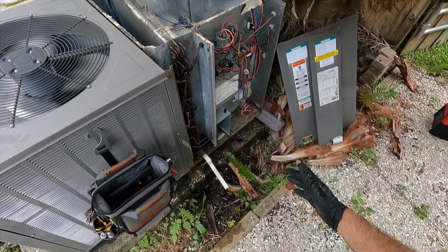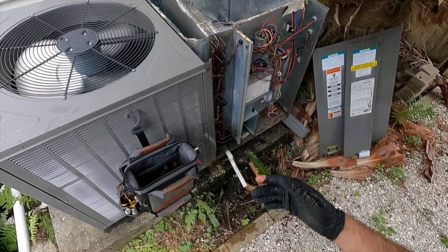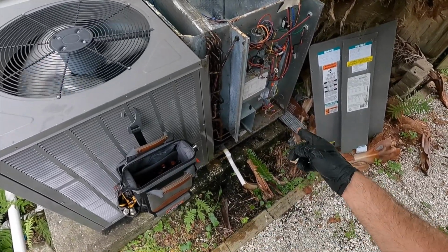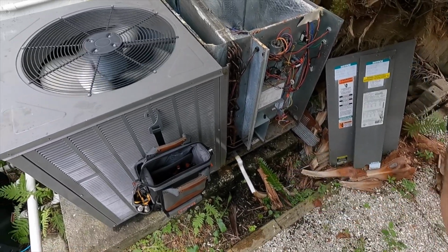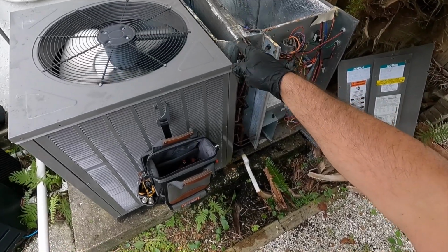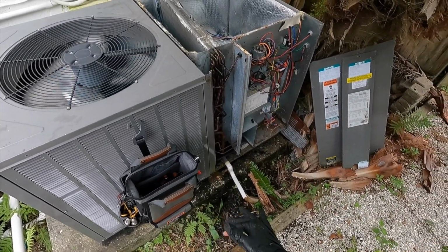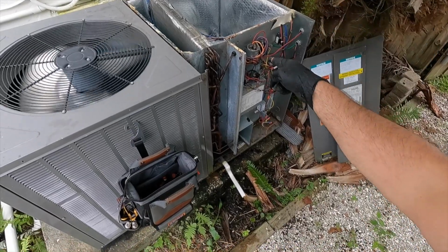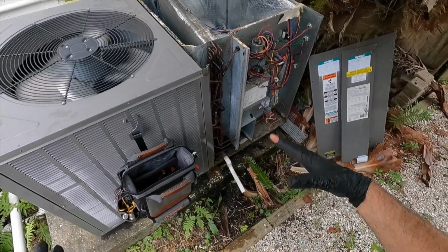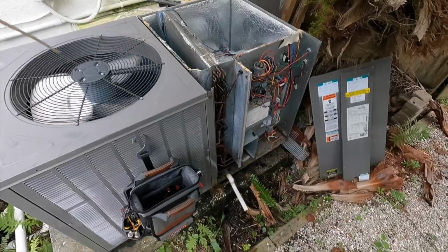So overall the health of the system's good as far as at least the measurements go. I will recommend a hard start kit for the start of the compressor, a UV bulb. It is glowing, but I know it's older than 2 years, so it's not producing UV anymore, so we'll go ahead and replace that. And then a deep clean for the bottom of the unit. So I'm gonna go ahead and tidy everything up, wrap it all up, and call it a day.